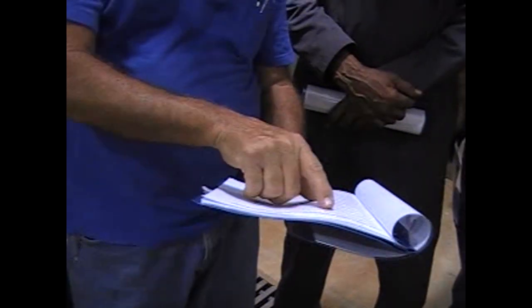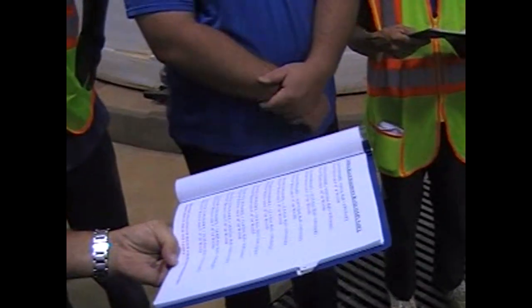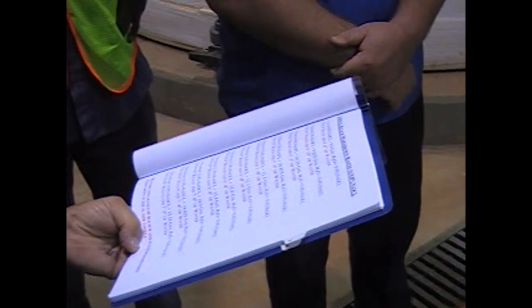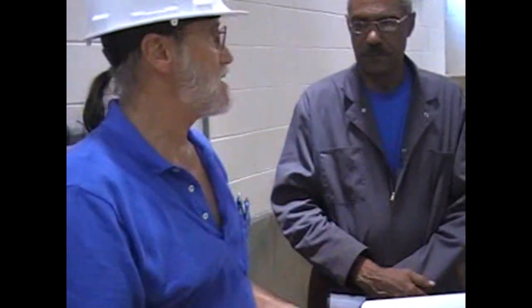This depends on the strength of your bleach, because you never know what strength of bleach they're going to deliver. That's one thing. Second thing is you're never going to know what strength of bleach you have in here as it sits. Now, fortunately, these are inside, so it's going to deteriorate less. But I'm going to tell you that hot bleach does deteriorate, and it deteriorates more rapidly than our product does. That 0.8 has less to lose, so it's a lot more stable product than hot bleach.